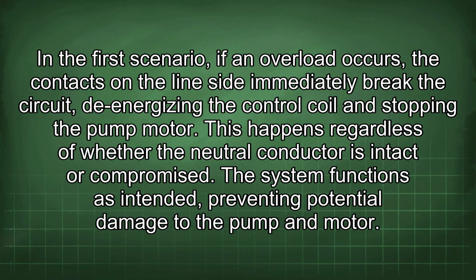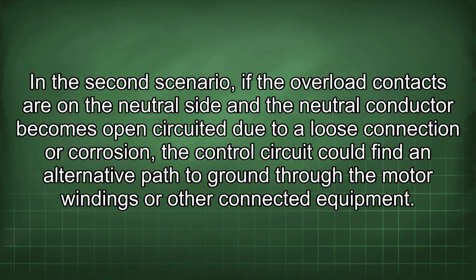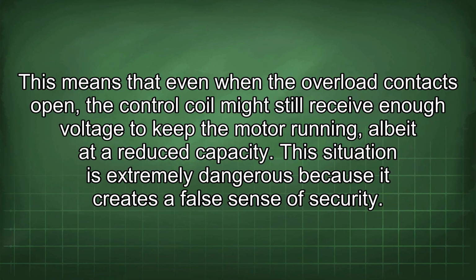In the first scenario, if an overload occurs, the contacts on the line side immediately break the circuit, de-energizing the control coil and stopping the pump motor. This happens regardless of whether the neutral conductor is intact or compromised. The system functions as intended, preventing potential damage to the pump and motor. In the second scenario, if the overload contacts are on the neutral side and the neutral conductor becomes open-circuited due to a loose connection or corrosion, the control circuit could find an alternative path to ground through the motor windings or other connected equipment. This means that even when the overload contacts open, the control coil might still receive enough voltage to keep the motor running, albeit at a reduced capacity.